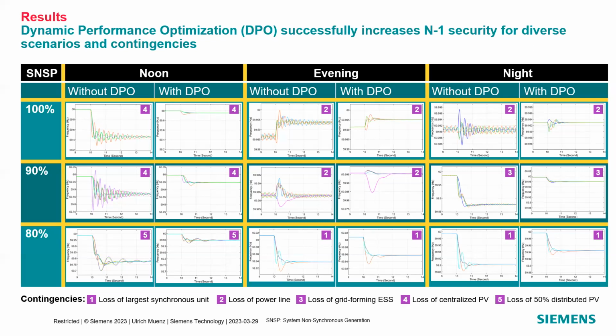We looked at different load and generation scenarios, very close to what HECO is doing today in planning studies: a noon case, an evening peak case, and a night case. We have different generation mixes measured by SNSP, system non-synchronous penetration. 100% means it's inverter only, 90% means there's one large generation unit, and 80% means there are two large synchronous generation units.